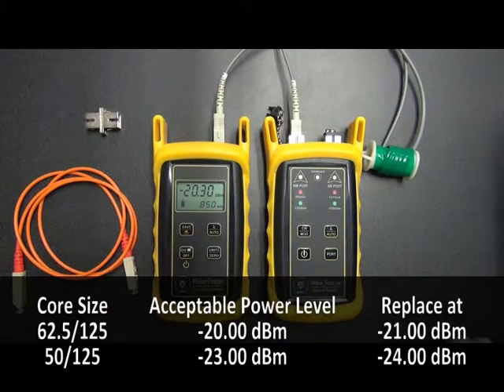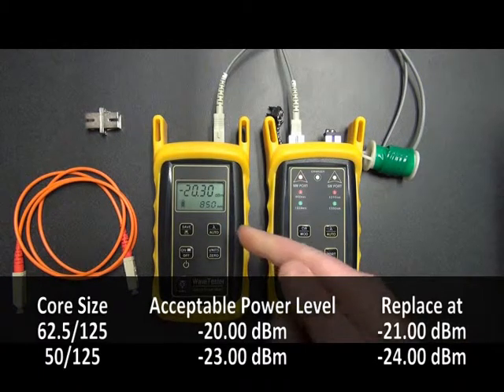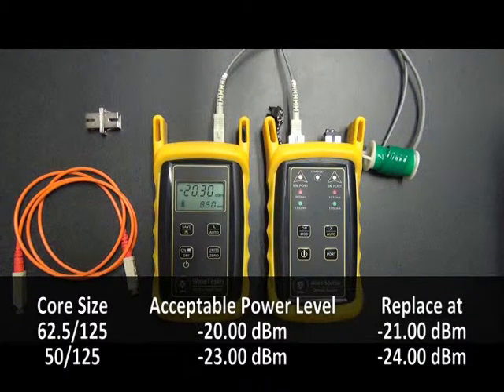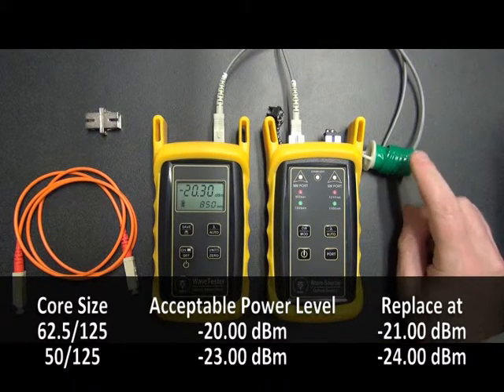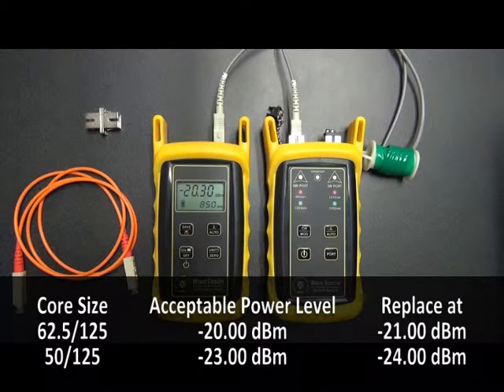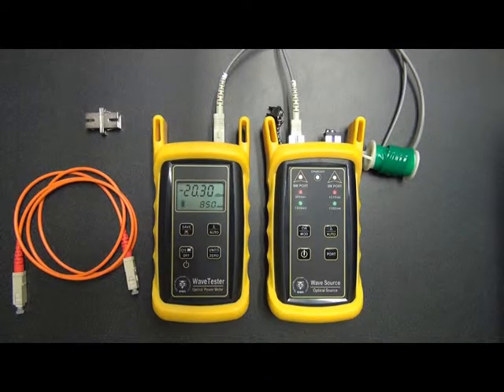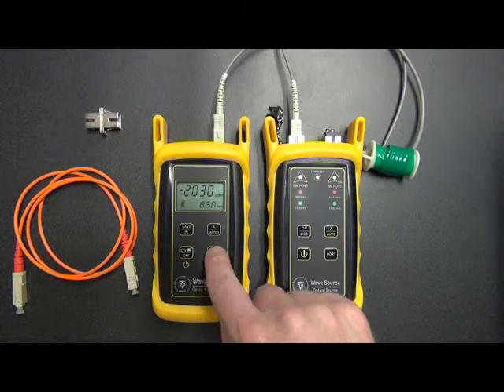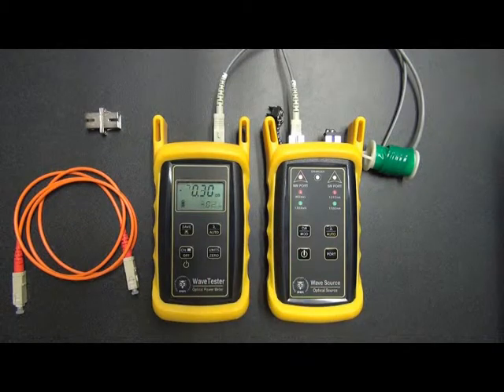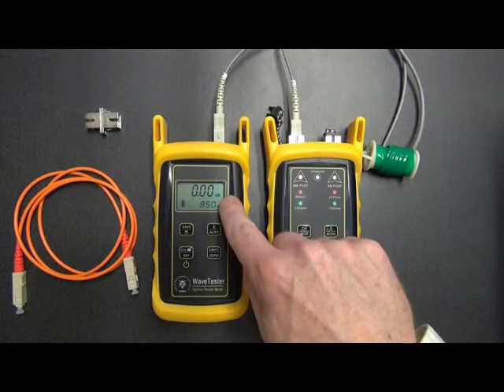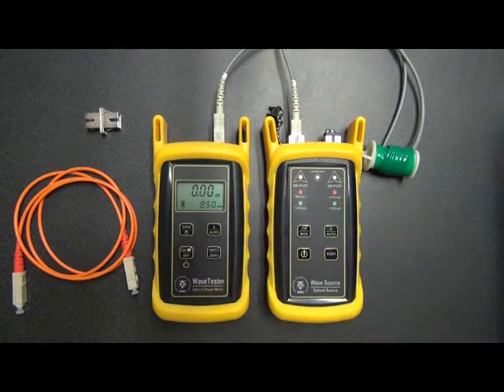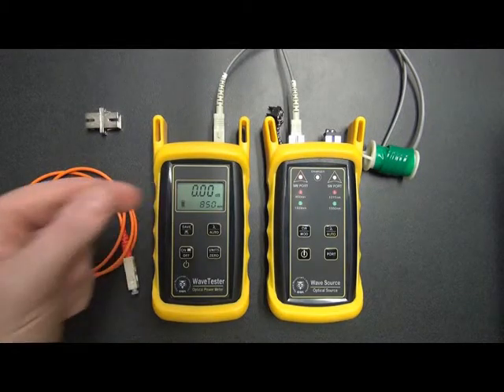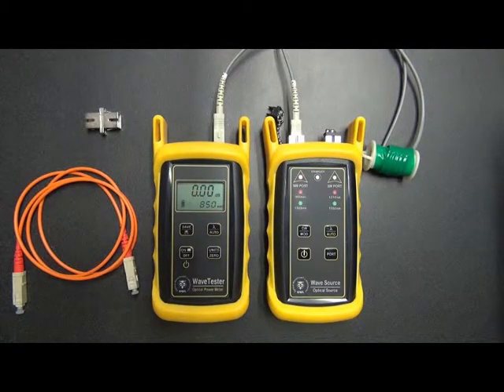Our target value is around minus 20 dBm. Now the reading could be a little higher or a little lower, as it is in this case, but as long as we're not exceeding minus 21 dBm, we know that this patch cable is sufficient for use. Okay, so we know this is a good reference level, so let's just temporarily zero out this wavelength. Okay, notice the reading switches to dB, and it says 0, so 0 dB. So this means minus 20.3 is our reference level, and it's where we're starting our measurement at 0 dB.